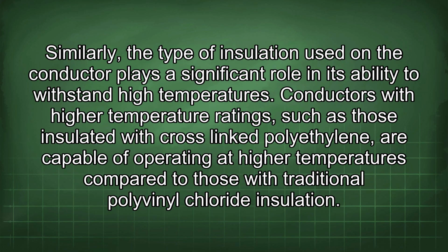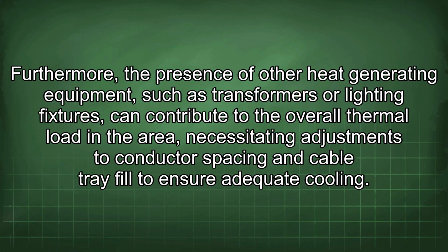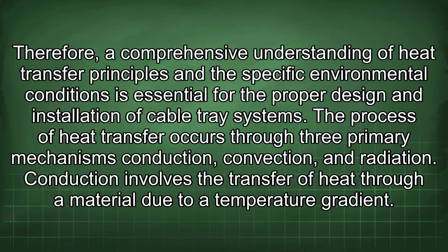Similarly, the type of insulation used on the conductor plays a significant role in its ability to withstand high temperatures. Conductors with high temperature ratings, such as those insulated with cross-linked polyethylene, are capable of operating at higher temperatures compared to those with traditional polyvinyl chloride insulation. Furthermore, the presence of other heat-generating equipment, such as transformers or lighting fixtures, can contribute to the overall thermal load in the area, necessitating adjustments to conductor spacing and cable tray fill to ensure adequate cooling. Therefore, a comprehensive understanding of heat transfer principles and the specific environmental conditions is essential for the proper design and installation of cable tray systems.